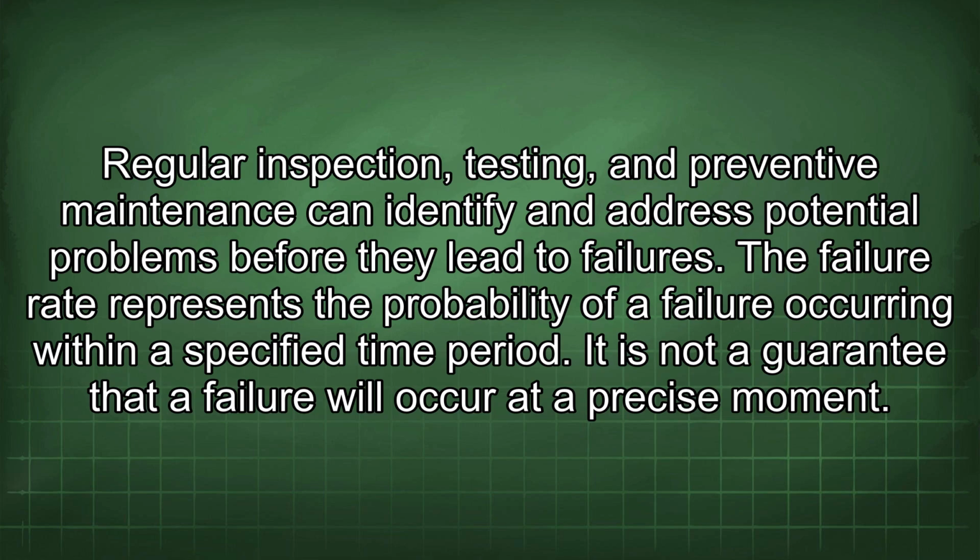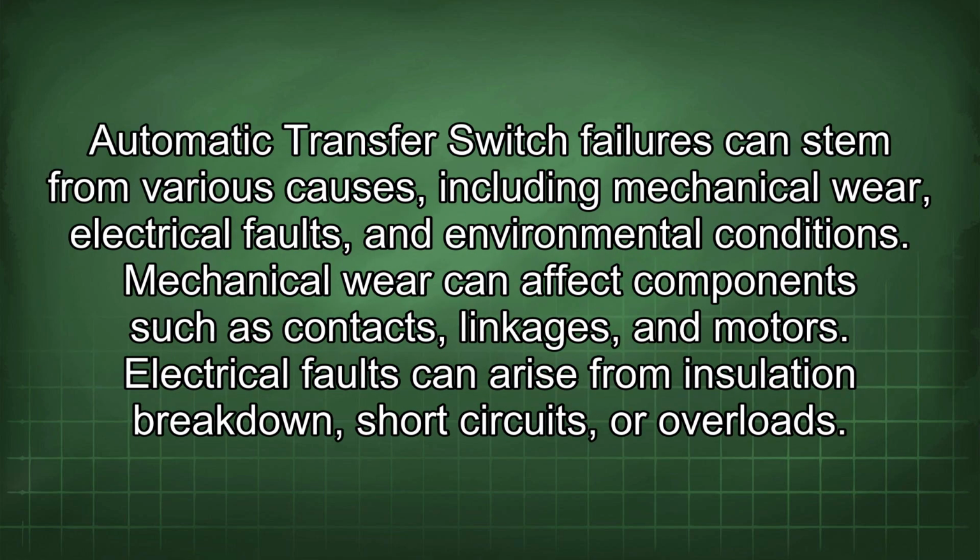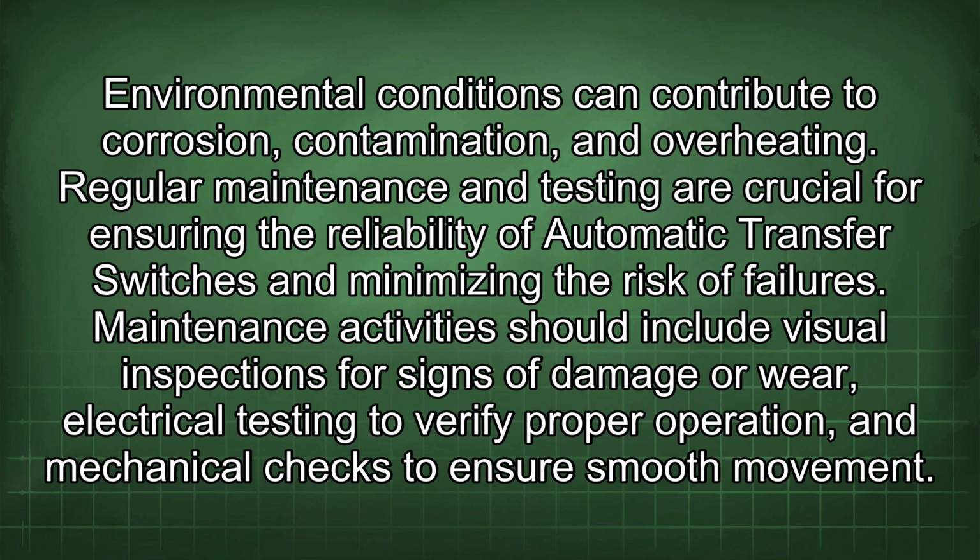The failure rate represents the probability of a failure occurring within a specified time period. It is not a guarantee that a failure will occur at a precise moment. Automatic transfer switch failures can stem from various causes, including mechanical wear, electrical faults, and environmental conditions. Mechanical wear can affect components such as contacts, linkages, and motors. Electrical faults can arise from insulation breakdown, short circuits, or overloads. Environmental conditions can contribute to corrosion, contamination, and overheating.